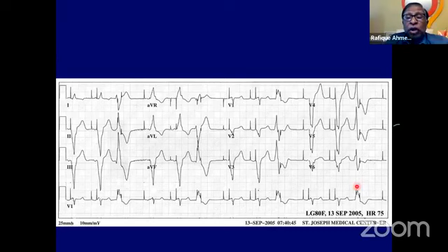So there is a feature built into the pacemaker. This AV interval is 160 milliseconds, but when this happened, it is 110 milliseconds. Pacemakers have a built-in feature that if, after atrial pacing, within the blanking period, there is a sensed QRS complex, the ventricle is paced instead of inhibited, and it's called safety window pacing. Many, many years ago, it used to be called the 110 phenomenon. We used to see these things in older pacemakers in the mid 80s, late 80s.